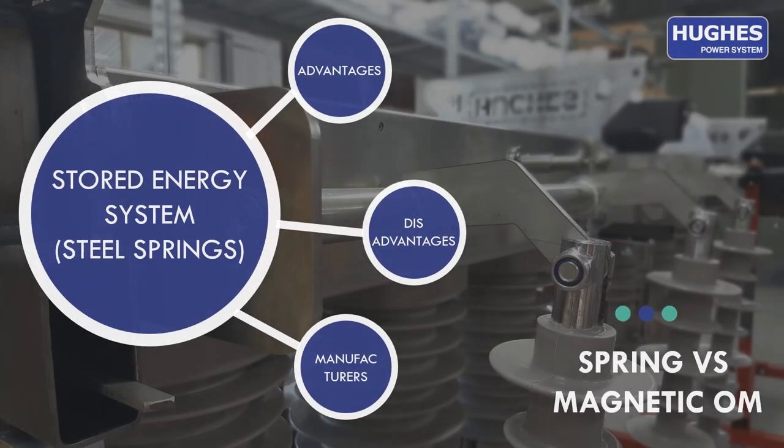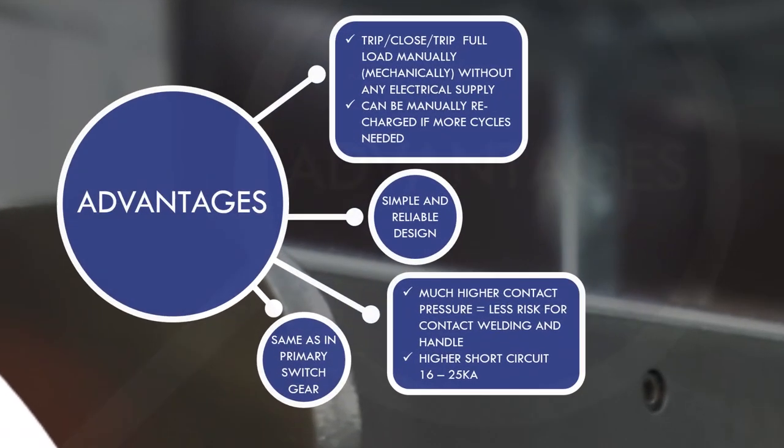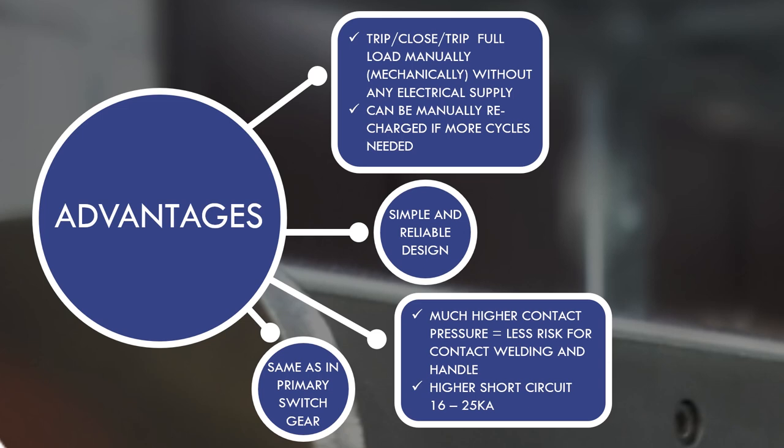Let's have a closer look at first type: spring operating mechanism, also called stored energy system. Basically, the biggest advantage is that you can still operate your switch module as many times as needed in case a protection relay is damaged or stolen. Operation trip-close-trip can be performed with full load manually with the help of hook stick without any electrical supply. It can be also manually recharged with the same hook stick as many times as needed. Next advantage is that it has a simple and very reliable design. Much higher contact pressure, which is equal to less risk for contact welding and handle, and higher short circuit with a range from 16 to 25 kA.